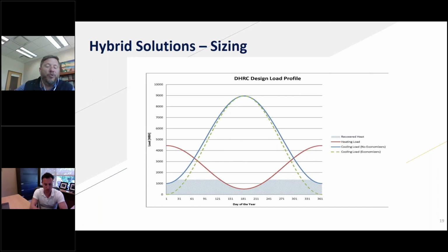And then if we think about our most efficient cooling method, we would want to be capturing the peak that is up here for the cooling load. And so again, that looks like now they're all tying into the same loop. It's all compressorized equipment, and what you end up doing is you say, let's pick the unit that is best suited for the operation we're asking it to do. And when we do that, we get the most efficient system overall.